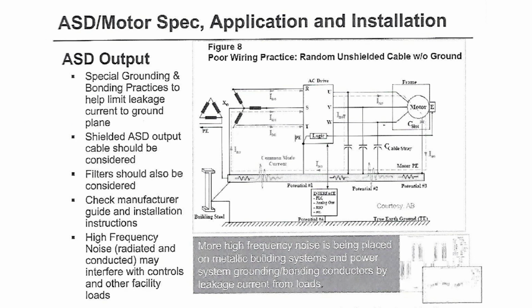Use aluminum. Well, you already seen them. We can put filters on the drive, and we can bond the motor. We can have a decent, effective ground system, and we won't have to pull up to the motor. Because if I put a filter on the output of the drive, I don't have that high frequency generated down the wire to the motor and then feeding back to the drive because of the high frequency bouncing off the impedance of the motor and heading back to the drive. So a high frequency going to the motor, hits the motor, bounces off the motor, and heads back to the drive. So it smokes the motor, smokes the drive.